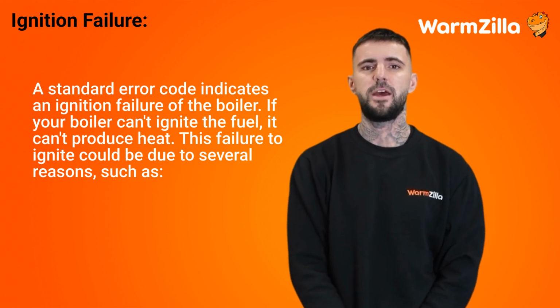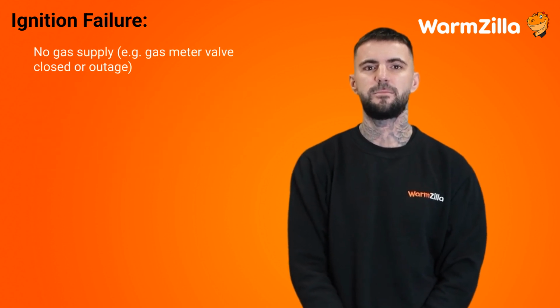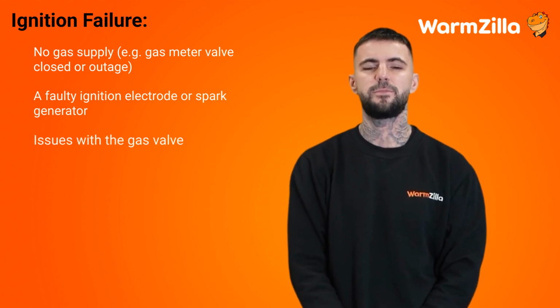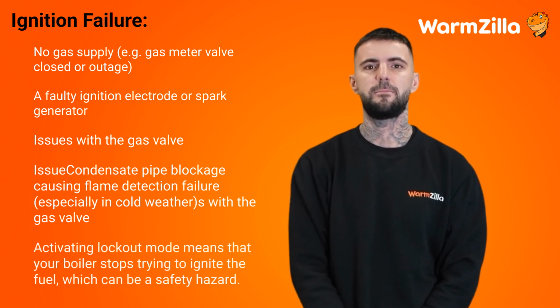This failure to ignite could be due to several reasons, such as no gas supply, for example, gas meter valve closed or outage, a faulty ignition electrode or spark generator, issues with the gas valve, condensate pipe blockage causing flame detection failure, especially in cold weather. Activating lockout mode means that your boiler stops trying to ignite the fuel, which can be a safety hazard.